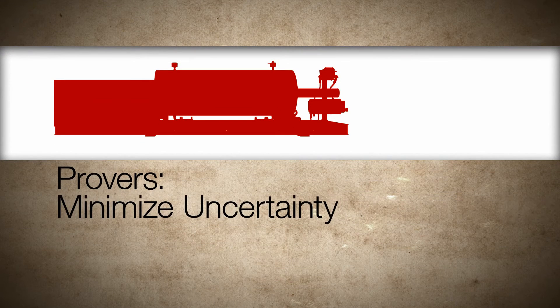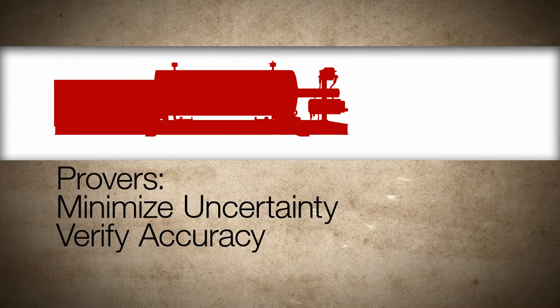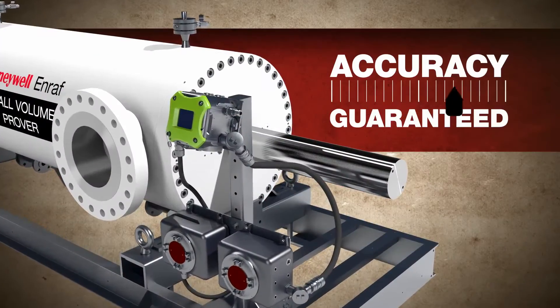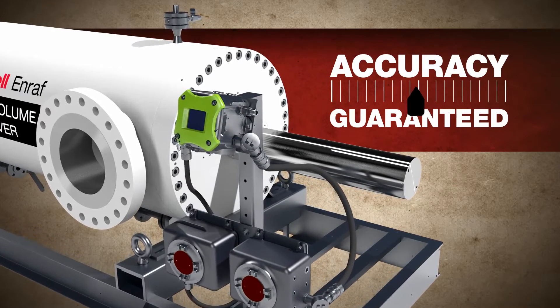To minimize the uncertainty, flow meters must be verified regularly using provers. This is the Honeywell Enraf Small Volume Prover, used for proving the accuracy of custody transfer and fiscal metering of oil, chemicals, and liquefied gas.